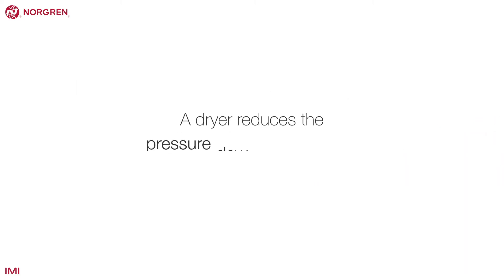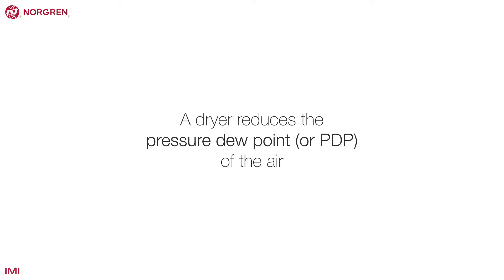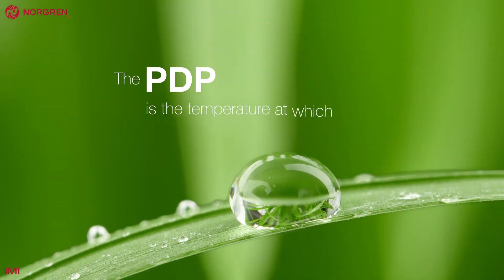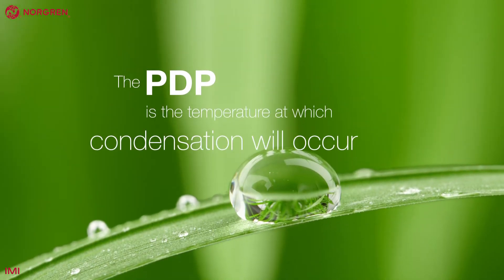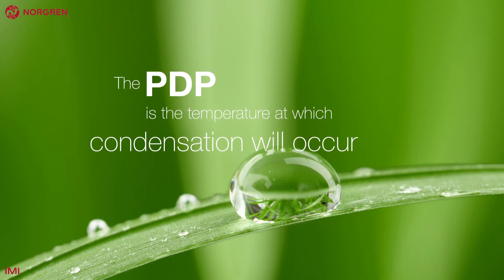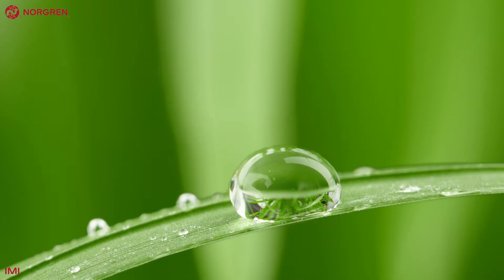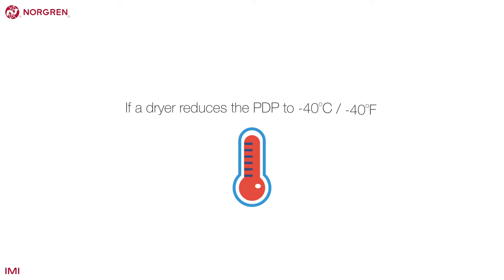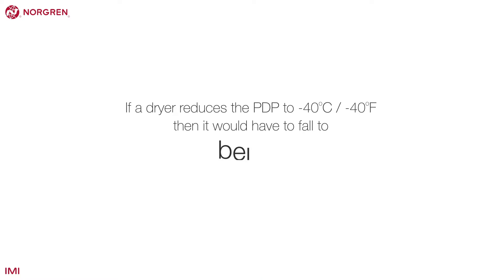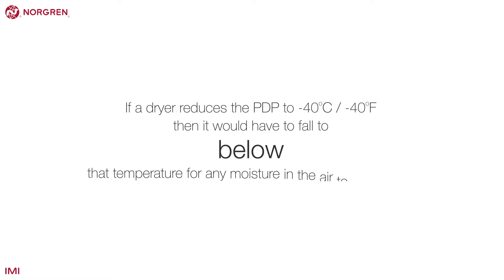A dryer reduces the pressure dew point, or PDP, of the air. The PDP is the temperature at which condensation will start to occur — it's the point at which the air can no longer hold all the moisture within it. If a dryer reduces the PDP to minus 40 degrees Celsius or minus 40 degrees Fahrenheit, then it would have to fall below that temperature for any remaining moisture in the air to condense to liquid.